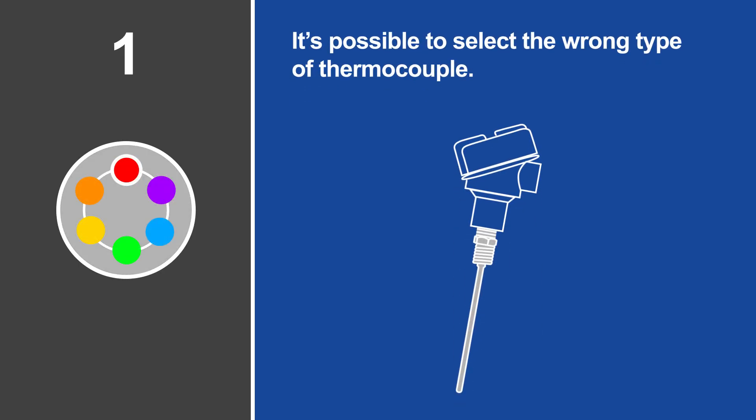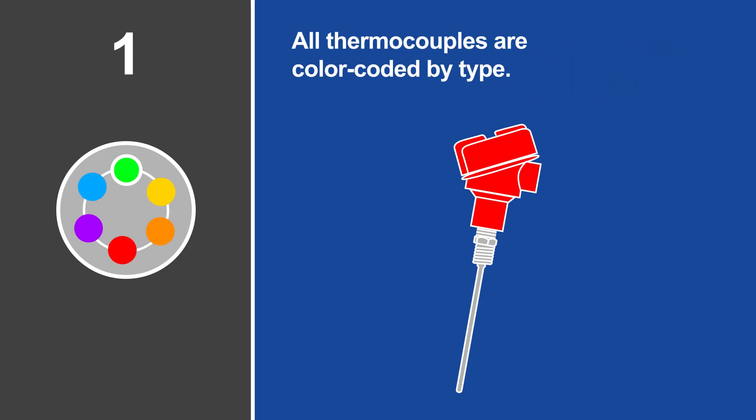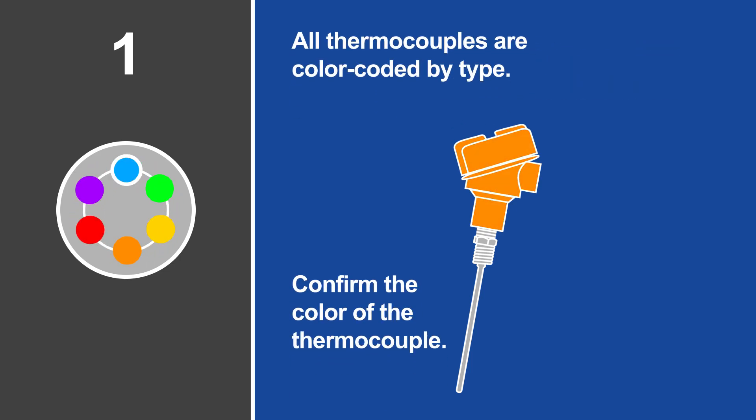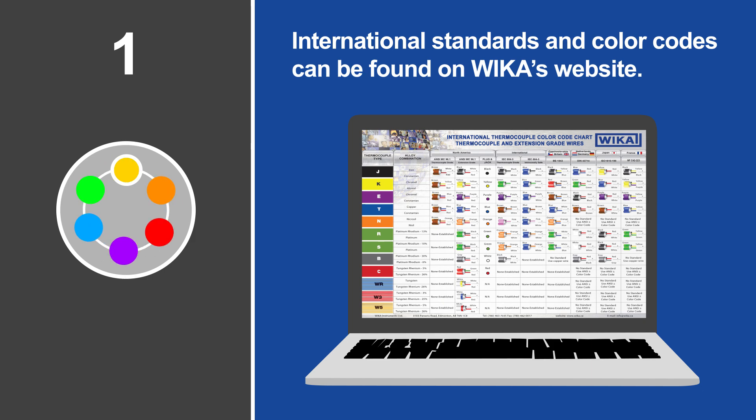When putting the settings into a transmitter during installation, it's possible to select the wrong type of thermocouple. Since almost all thermocouples are color-coded by type, you need to confirm the color of the thermocouple jacket and match the settings on the transmitter to solve this problem. International standards and color codes can be found on WIKA's website.